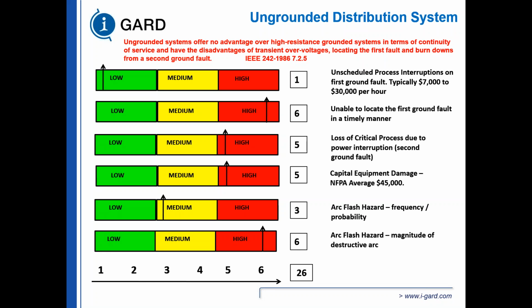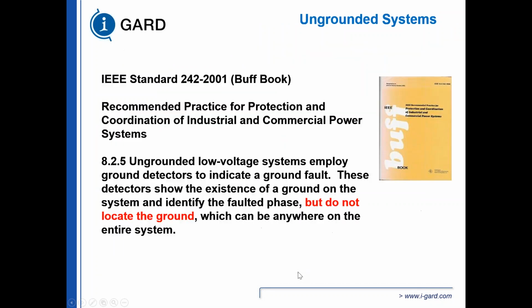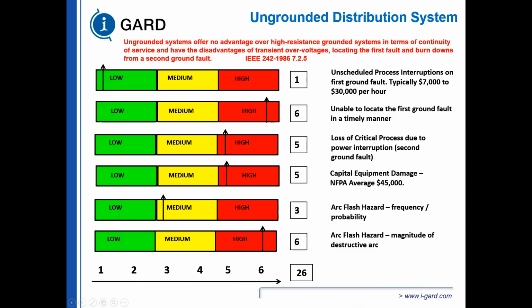So this is where I get a little bit annoyed, because people choose ungrounded systems because they can't tolerate any kind of power interruption. However, to find the fault, you need a power interruption. Loss of critical process due to power interruption on the second fault is high, because it's so difficult to find where the fault is on the first fault, people don't look for it. So the probability of having a second fault that occurs on another phase is quite high. Capital equipment is high. Arc flash frequency and hazard is low to medium, and arc flash magnitude is high because it's based on the 3-phase bolted fault current. So the risk meter is equal to 26, and that's quite high.